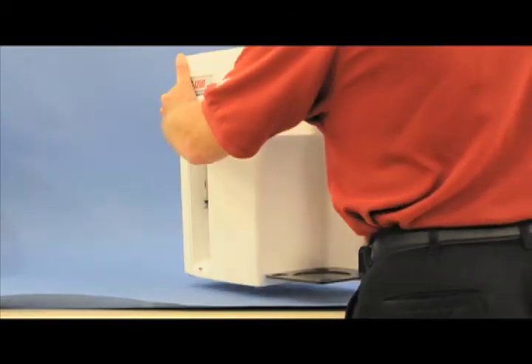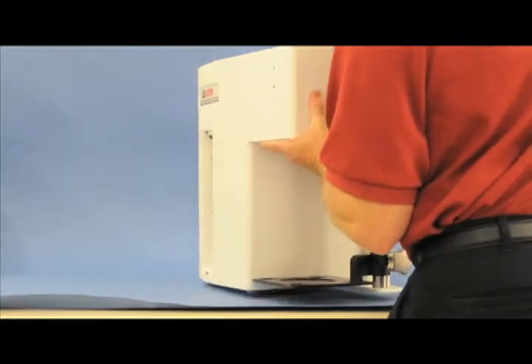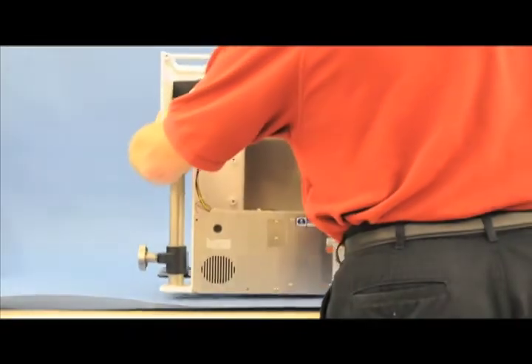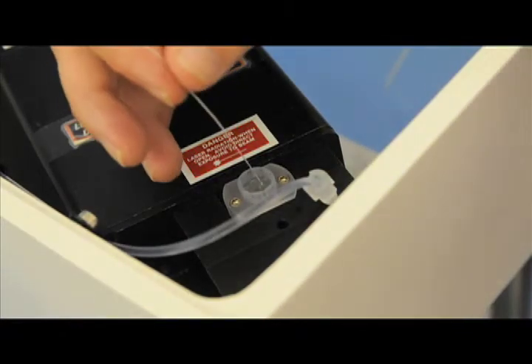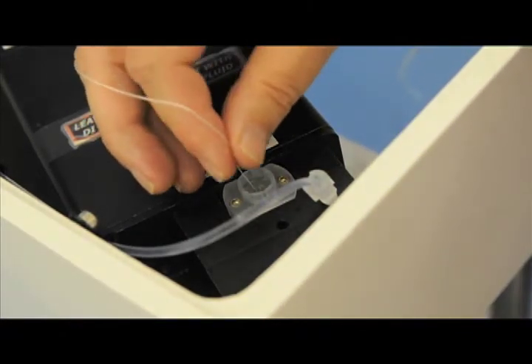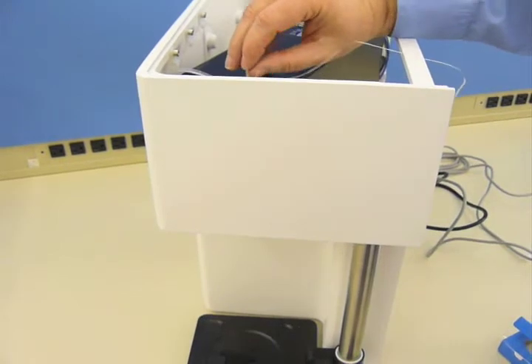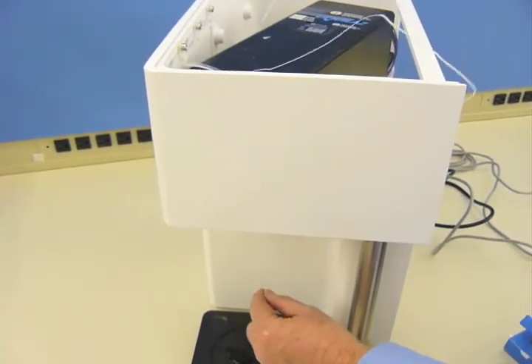First, I will turn the sampler around so you can see the next step, which is to thread the floss through the capillary. Feed the long compressed end we identified earlier into the top capillary fitting. Keep feeding it through until you see it begin to exit the lower fitting on the sampler chassis.